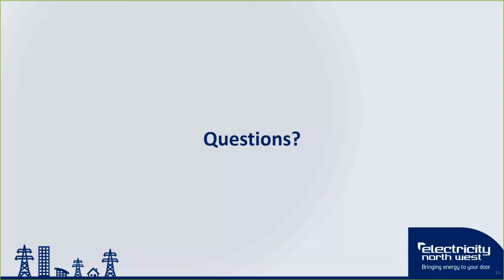Where you have a larger heat pump system, which is simply controlled by sequential one-off switching of a number of compressors, i.e. no inverters, why would we need harmonic emission currents? The answer is we probably wouldn't, because there's no likely source of harmonic currents. What we would need to consider is flicker and step if you've got a number of compressors effectively direct online starting. So it's a good question. I think that the focus would be more on the voltage rather than the harmonic currents.